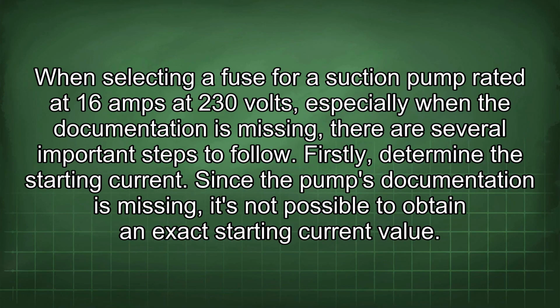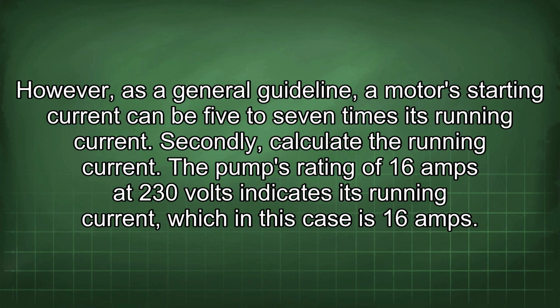When selecting a fuse for a suction pump rated at 16 amps at 230 volts, especially when the documentation is missing, there are several important steps to follow. Firstly, determine the starting current. Since the pump's documentation is missing, it's not possible to obtain an exact starting current value. However, as a general guideline, a motor's starting current can be 5 to 7 times its running current.